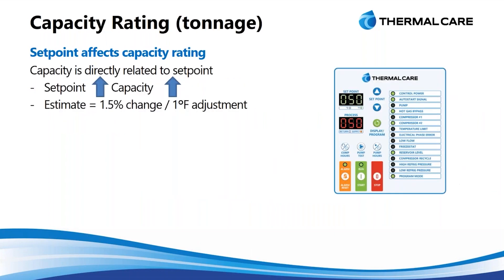I bring up the nominal rating because certain things affect the capacity of the unit, and you need to be aware of those when selecting your chiller. The first and most important is usually the first question I ask when starting to design a system: what is the temperature of the water required for the process? When you change away from that nominal 50-degree set point, you actually change the capacity of the unit. As demonstrated here using a nominal 10-ton chiller as an example, as we increase that set point, we actually gain a percentage of capacity with each degree. We can get up to almost an additional whole ton of cooling by raising the set point temperature by five degrees.